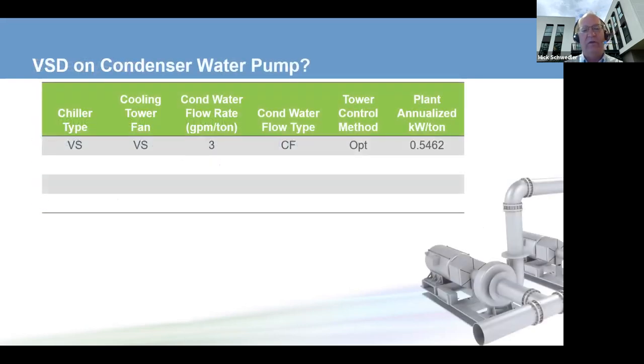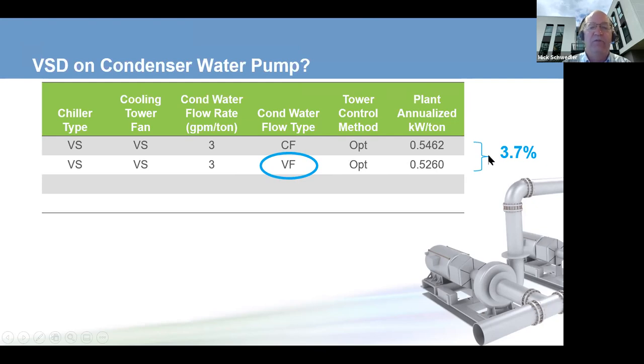So in a particular case, we took this and we have a variable speed chiller, a variable speed cooling tower fan, and a constant flow condenser designed at 3 GPM per ton. We control our cooling tower to optimize the sum of the chiller plus tower energy consumption, and our annualized operating kW per ton for the plant, without the chilled water pump but with the chiller, condenser water pump, and cooling towers, is 0.546 kW per ton. Pretty good. So what happens if we can reduce and vary the condenser water pump speed? Are there savings? The answer is yes, because there are some times when we can reduce the condenser water pump's speed, reduce its flow rate, reduce the condenser water pump power, and we save in the range of 3.8, about 4% of your chiller plus condenser water pump plus cooling tower fan energy annually. So on an existing system, this is something that we might want to look at.